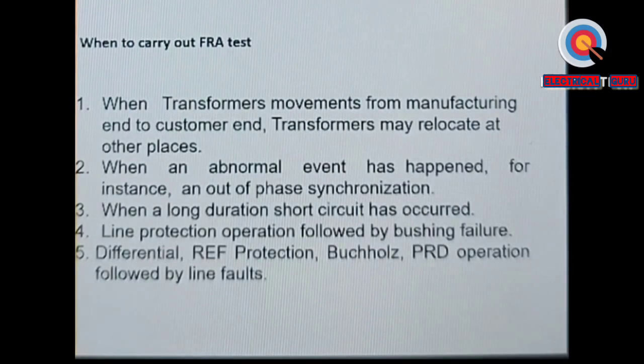So nowadays, for most large transformers, it is a practice, not mandatory but a practice, to test the transformer after mounting it on the trailer for transportation. Then we have a reference signature, because these transformers are most of the time transported without oil, so we carry out this test without oil. So we have a reference signature of the transformer geometry when loaded on the trailer.